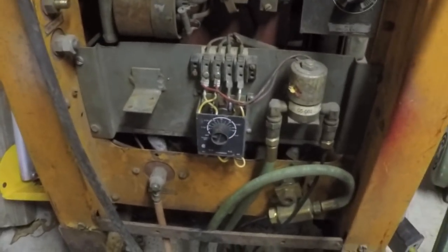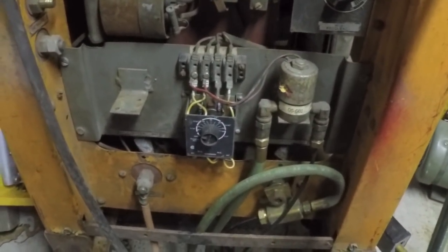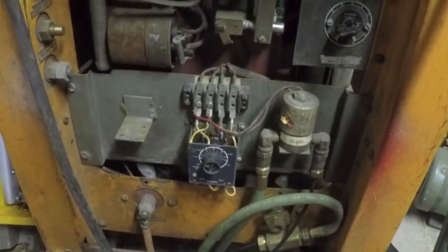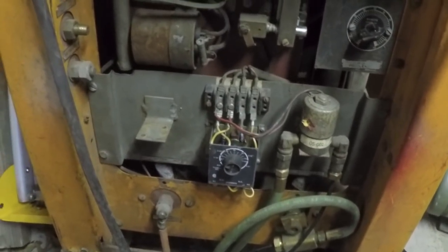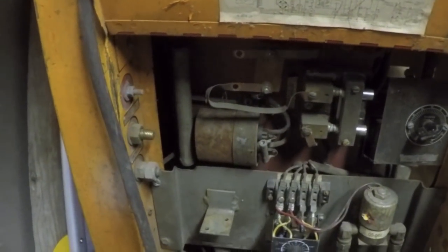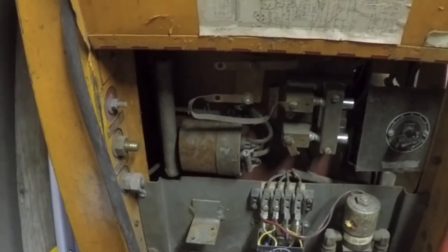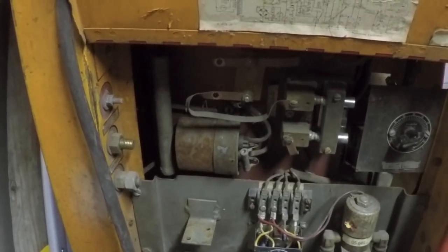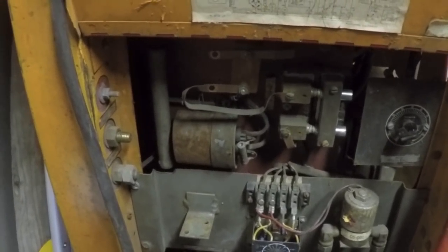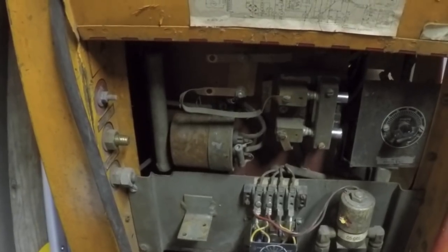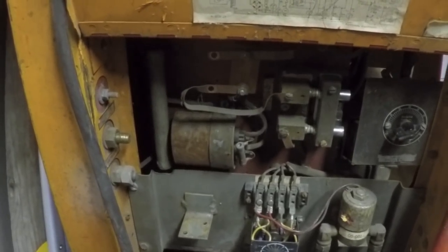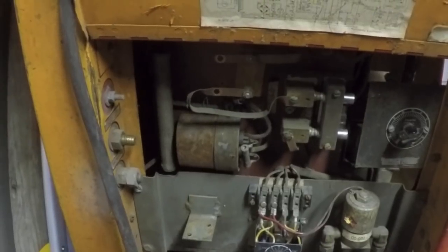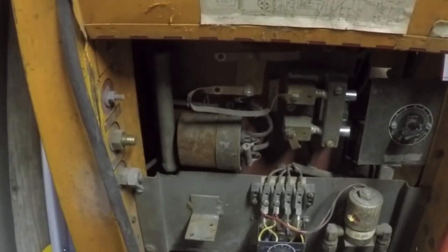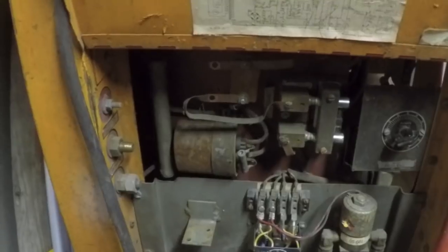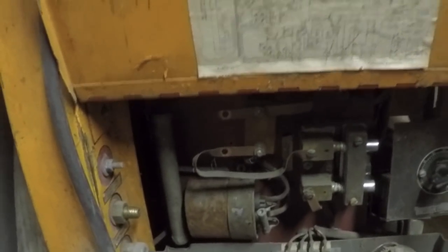Alright, I didn't see any signs of arcing or anything inside there. So now I've decided to go back and try removing one of the two capacitors to see if one of them is breaking down. If I'm lucky and only one was causing the problem, having just one in circuit should show an improvement, and I'll know that capacitor, even though it tested okay out of circuit, is actually breaking down. So let's fire this up with one capacitor in and see what happens.